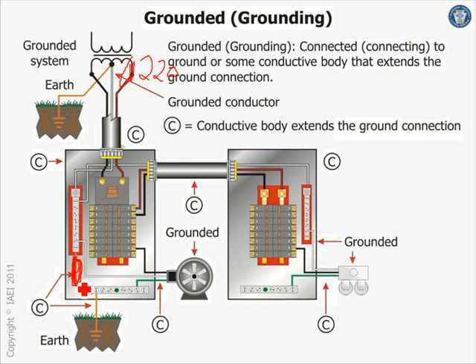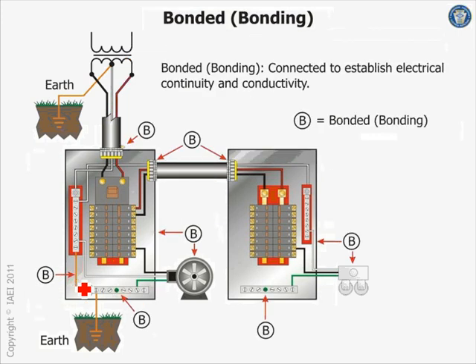So that's your bonding. Can you see the same system in grounding? These two are bonded together through the conduit and the bushings here, and grounded together, right? And this conduit is grounding this piece of equipment to the grounding electrode, to the grounding system that you have here. So bonding and grounding are almost interchangeable in a lot of applications. Any comments, guys? Any questions? Comments? See, I'm bonding the frame of this air handling unit to the frame of this panel through an equipment grounding conductor, or it could be the EMT conduit, or so forth.